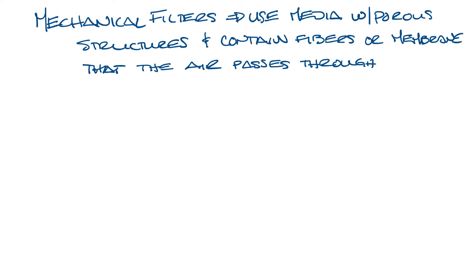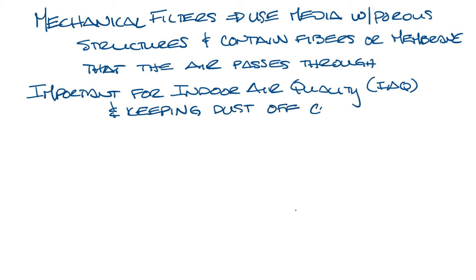Originally HVAC filters were used in the 1930s to keep dust and other particles off electric heaters. If you've ever been the first one to turn on electric heat at the beginning of the heating season, you know that smell of burning dust off of elements. But now filtration is also important for indoor air quality, IAQ. But it is still important to keep dirt and dust off of HVAC components. Water coils and fans are less efficient when they get dirty.